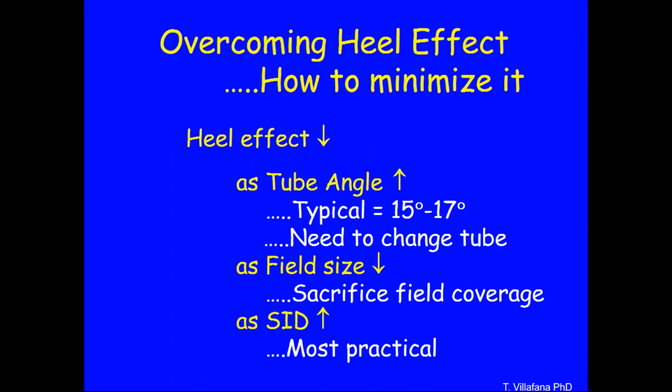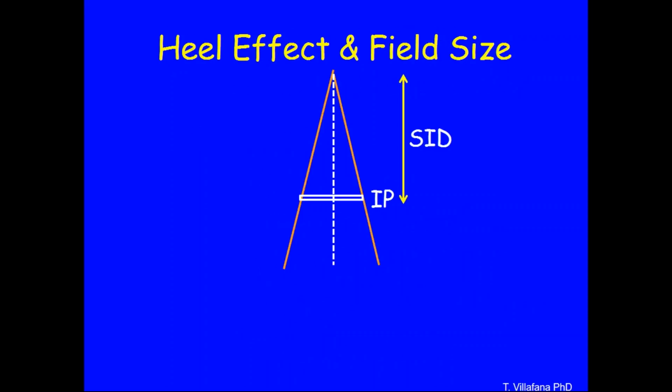Or you can increase the SID. That's the one they look for on the boards. If you see a heel effect, how can we minimize it or eliminate it? Change your SID. And here's a picture of what we're talking about.